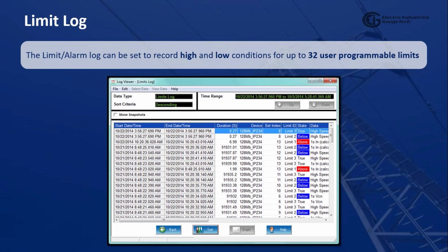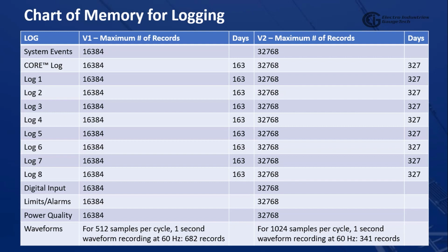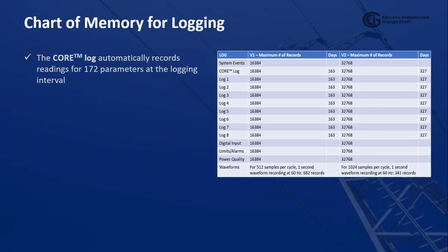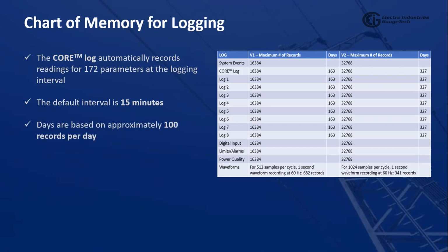The image here shows the log viewer, limits log. In addition, you can view the chart of memory for logging. It shows the log type, V1 maximum number of records, days, V2 maximum number of records, and days. The core log automatically records readings for 172 parameters at the logging interval. The default interval is 15 minutes.